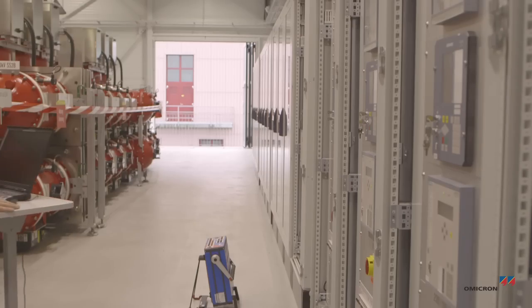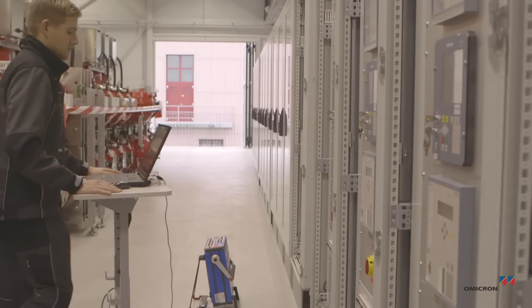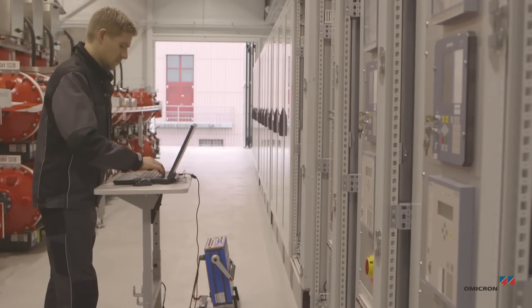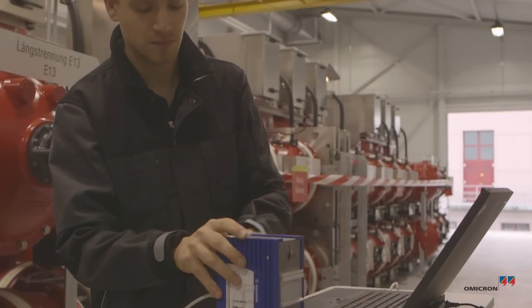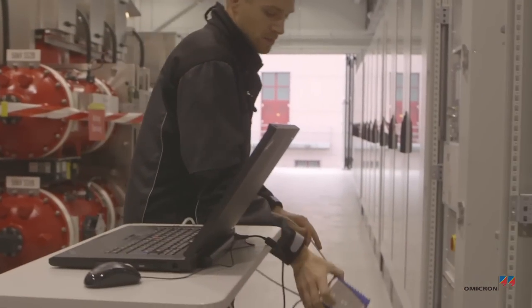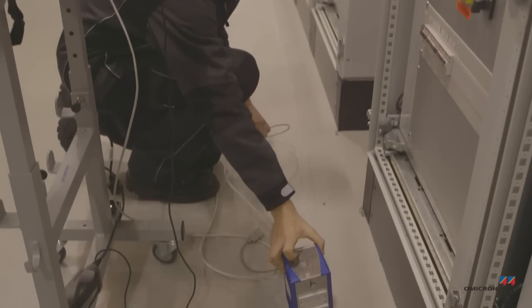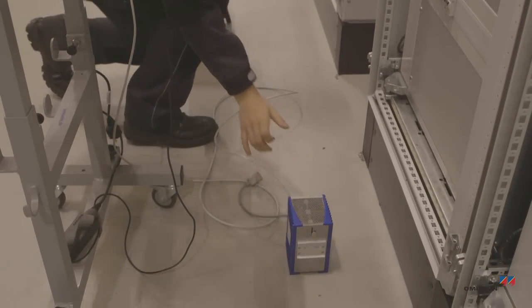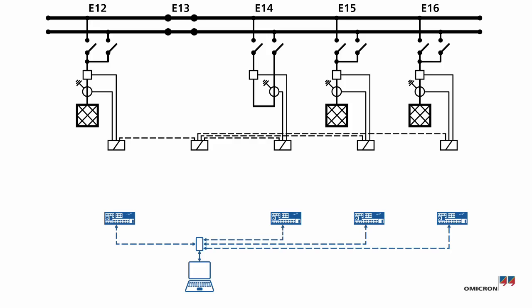Florian uses his laptop to control the entire test with RelaySimTest. He connects his laptop to all of the CMC test sets with a PTP transparent switch.